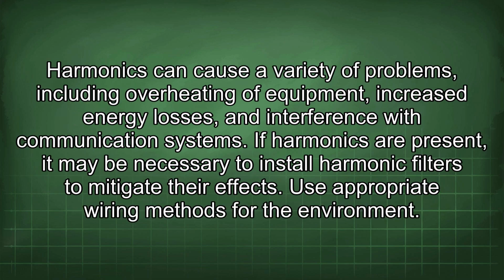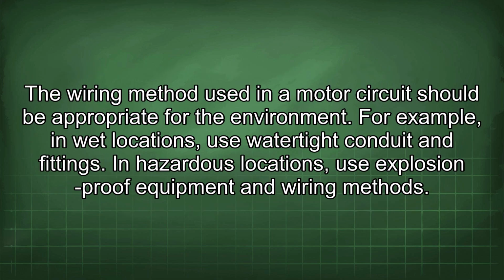Harmonics can cause a variety of problems, including overheating of equipment, increased energy losses, and interference with communication systems. If harmonics are present, it may be necessary to install harmonic filters to mitigate their effects. Use appropriate wiring methods for the environment. The wiring methods used in a motor circuit should be appropriate for the environment. For example, in wet locations, use watertight conduit and fittings. In hazardous locations, use explosion-proof equipment and wiring methods.